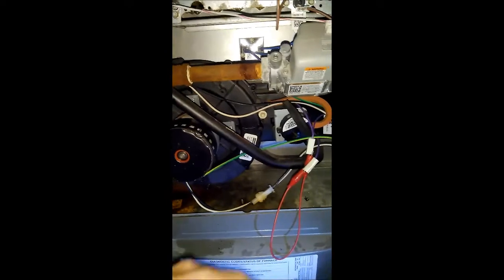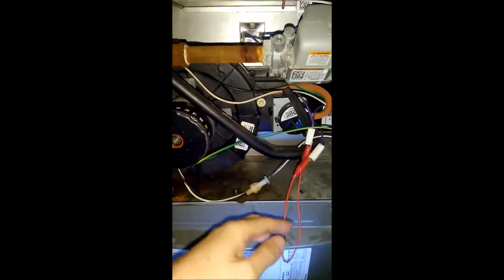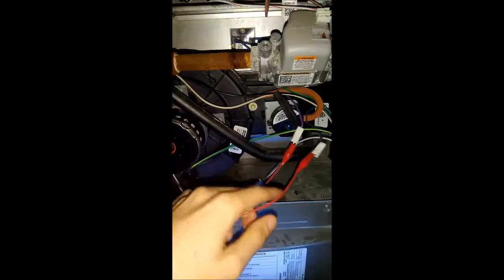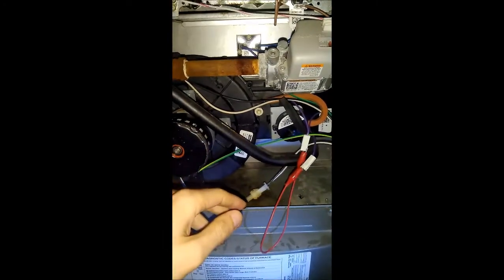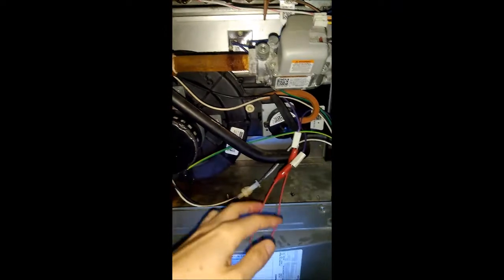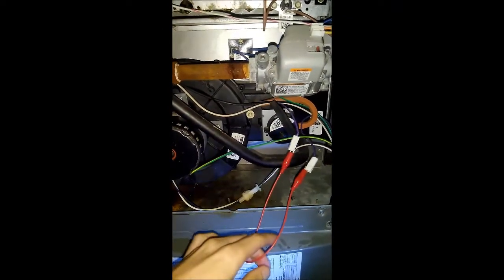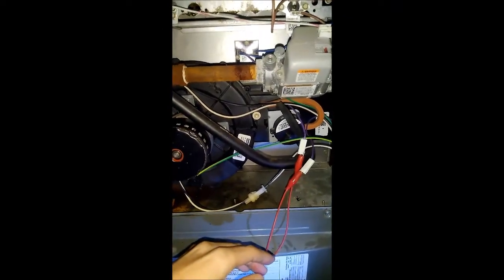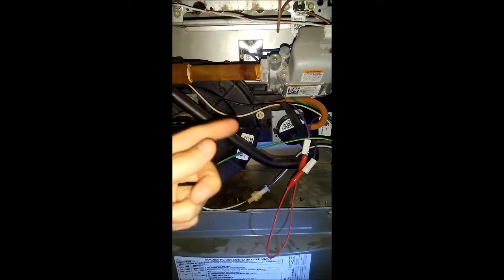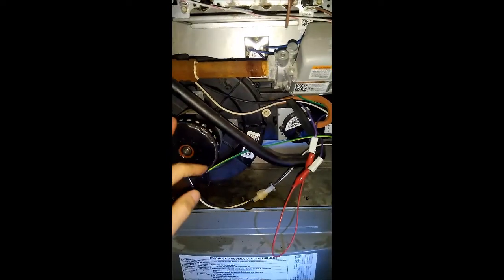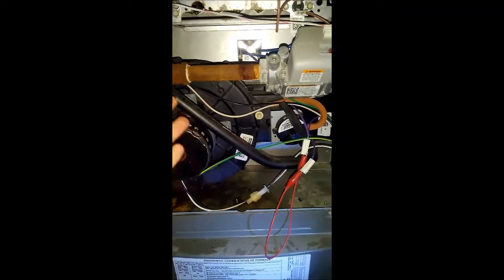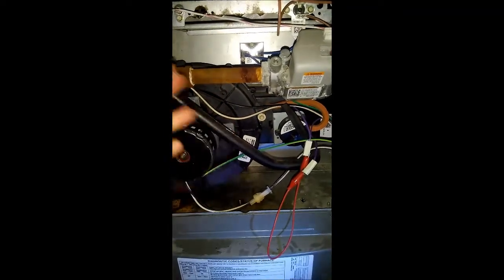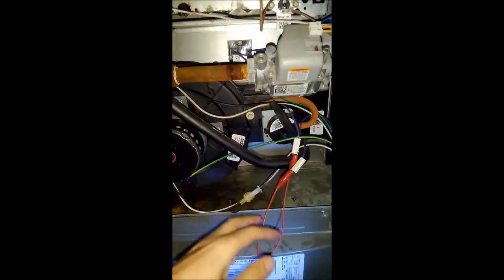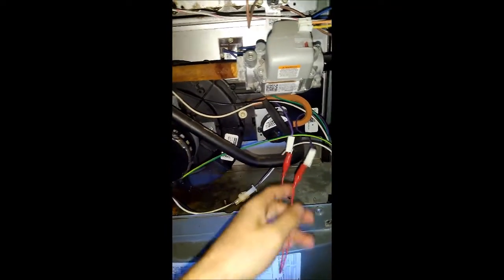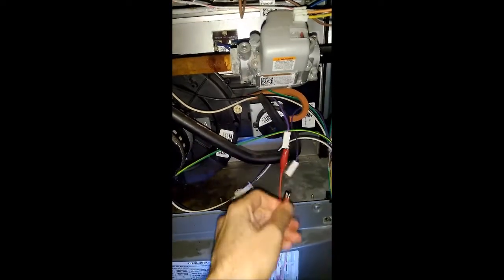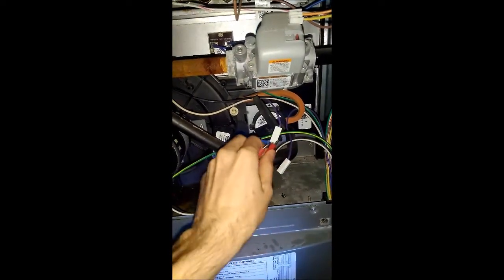So, a simple way you can check to see if it's your sensor or not is just take the leads off the sensor there and short them out. If the sensor's busted, then simply shorting the leads out like this will make the furnace think that the sensor is working, and it'll start up your furnace. Make sure that your blower is working when you do this, otherwise you'll have flames backing up into your house and carbon monoxide and all that good stuff. So it's very dangerous. You shouldn't do it except for diagnostic reasons, which is why I'm going to disconnect this, because I've already tested it a long time ago and I know what's wrong with mine.